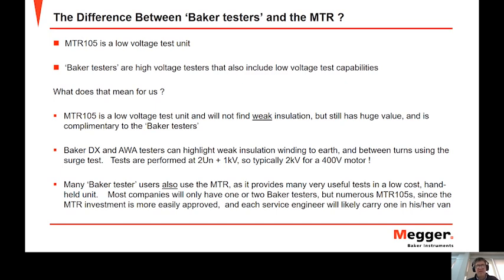But the MTR is a low voltage test. And what does that mean for us? It means that because it's low voltage, it's not able to find weak insulation. So when you're talking about motor reliability, to be sure that the motor will be reliable from the winding point of view, you need to be able to apply high voltage to find any developing weaknesses. So the MTR won't be able to do that, but it still has huge value, and it's extremely complementary to the Baker testers.